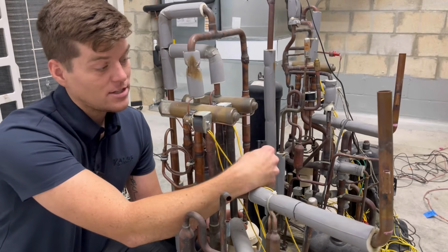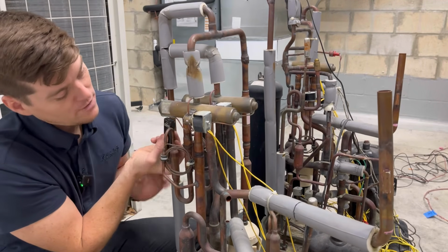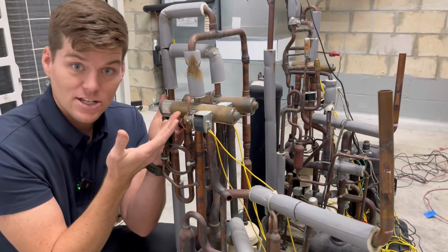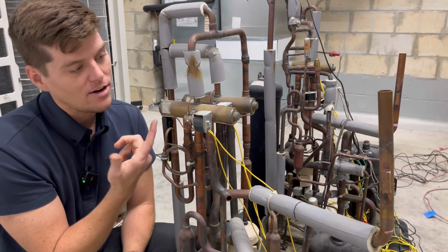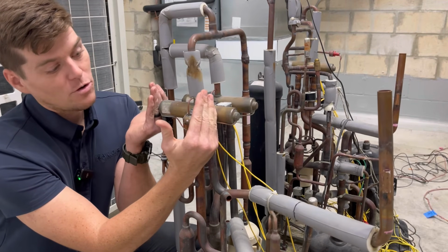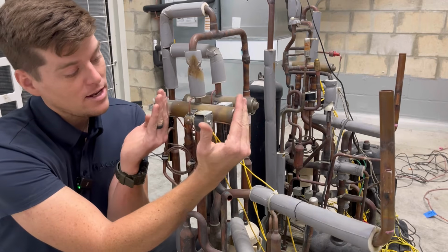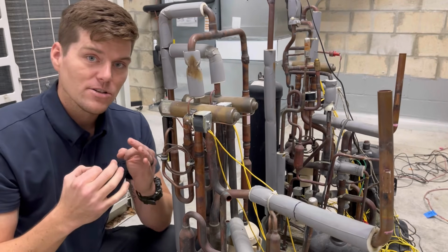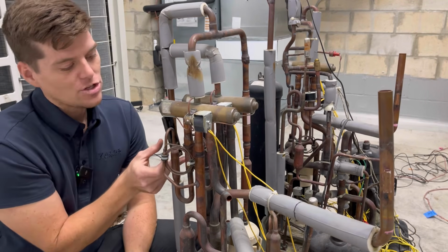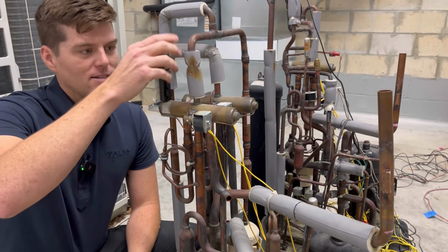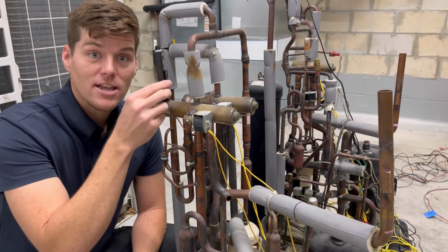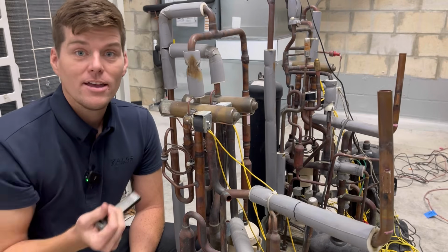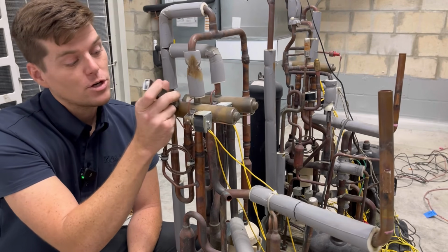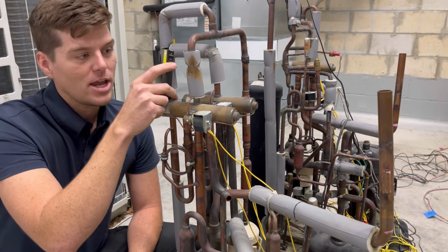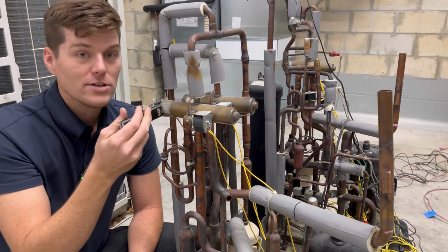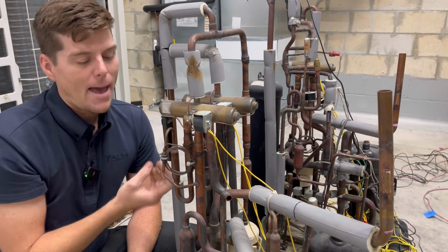Again, it's an easy check to just take a strong magnet on the end of your four-way valve and see. You can see it's shifted all the way to the left because it's sticking on the end here. The same is true. There's an internal mechanism that is going to slide from left to right, and because of that, the end seals on it are magnetic. And so I can check that with a simple magnet to see, hey, looky there, it actually sticks. If I put it here in the middle, it falls right off. There is nothing here for it to grab except for at the end of the chamber. This is how we check four-way valves and their positions with a magnet out in the field.